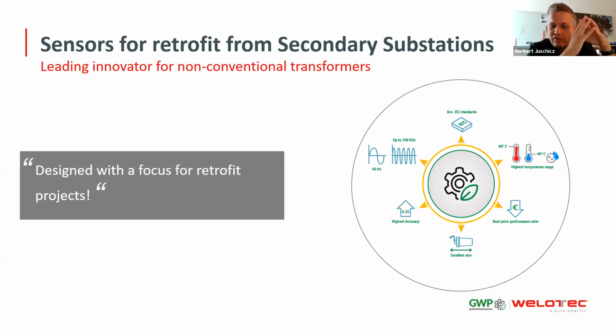Most important for this first part in the chain is that you have a passive system. Utility companies, the end customers, are used to having an instrument transformer, which can easily last 30 to 40 years. So it would be impossible to convince an end customer to build in an active sensor with active electronics, because then you're in a situation where this technology, this solution, will last a maximum of 15 years. Then you're at the end of lifetime. So for this reason, we are going for passive technology.